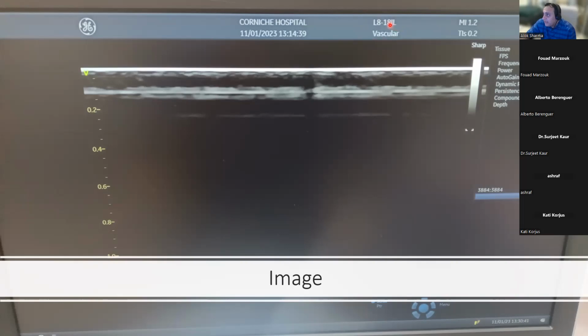Now, if I default to the vascular setting, it automatically defaults to a frequency of 9. It doesn't give me any auto gain at this particular point. I'd have to press the auto gain button, but it defaults to a dynamic range. And it gives us a few things like the depth, which is 1 centimeter. Clearly, this is the vascular small part setting. This is not great for looking at the lung because it's only 1 centimeter. But if I want to see superficial blood vessels, this is fantastic.